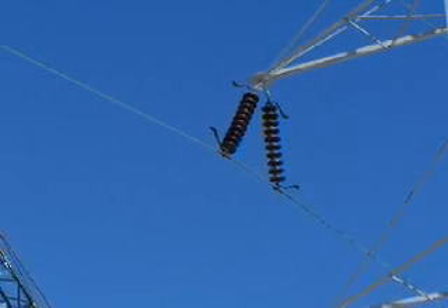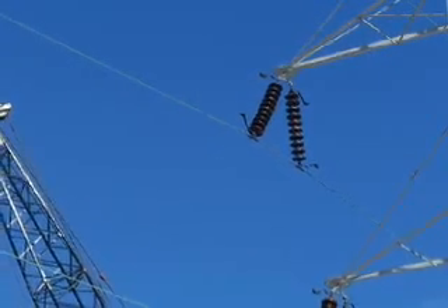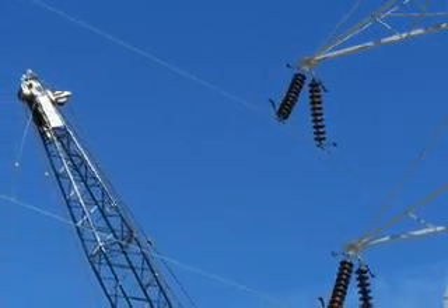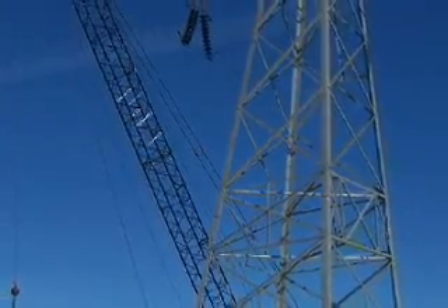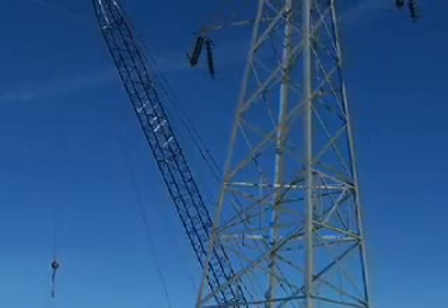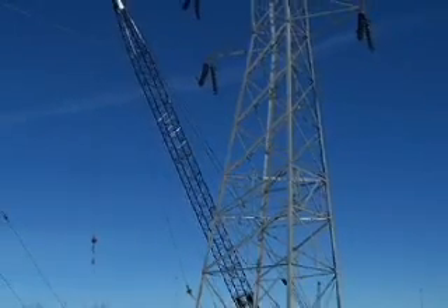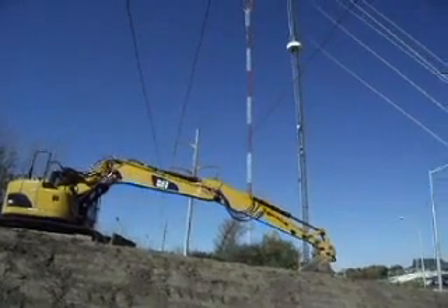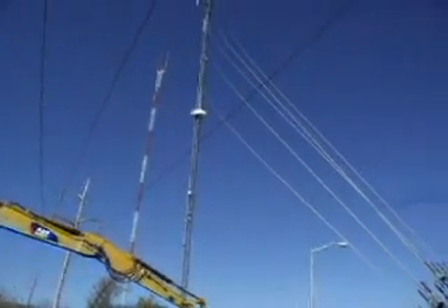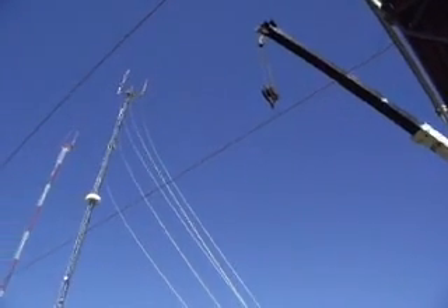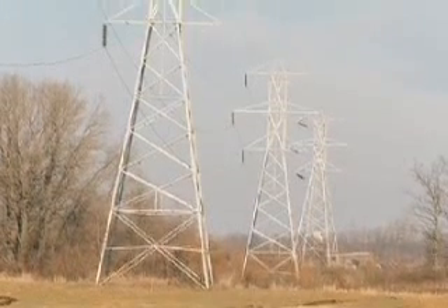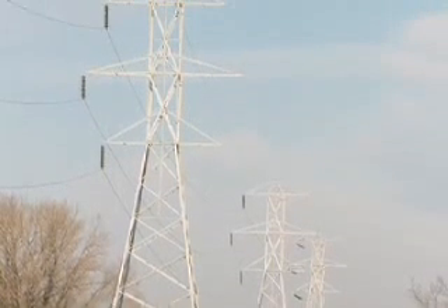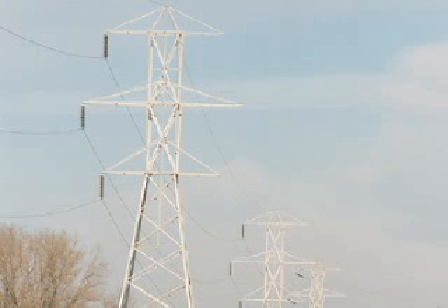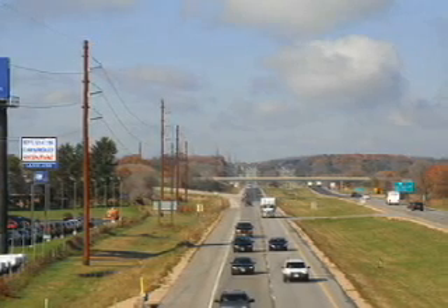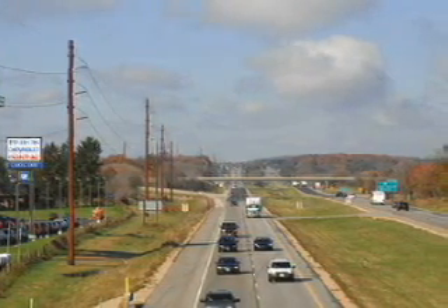There are OSHA standards for safe work clearances near high-voltage transmission lines. These clearances range between 10 feet for 69,000-volt lines to 16 feet for 345,000-volt lines. New OSHA rules require additional clearance for power-operated equipment used to hoist, lower, and horizontally move a suspended load. It's vital that you know how much clearance is between you, your equipment and tools, and the transmission line at all times.